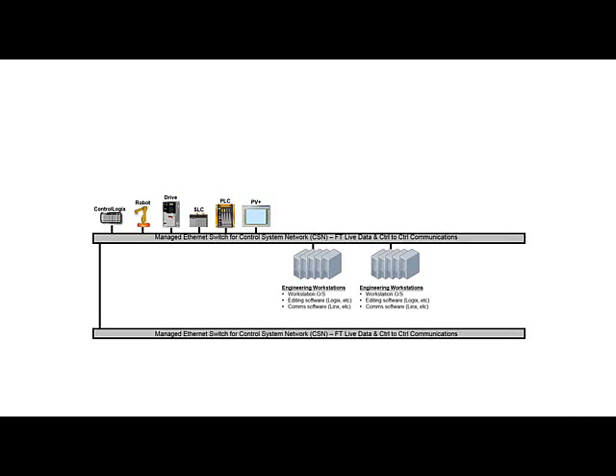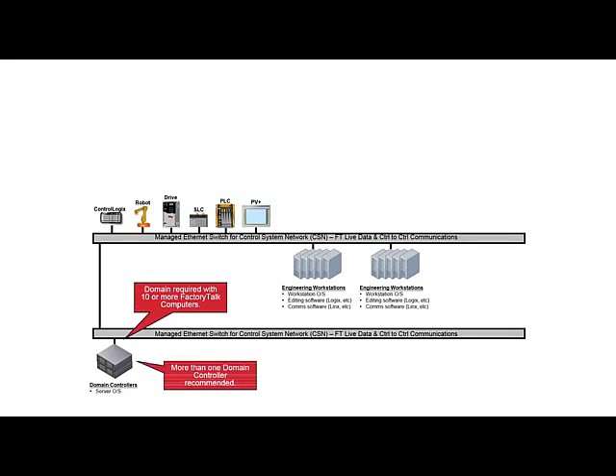Taking the network infrastructure as read, the first thing to consider is the Windows infrastructure. In this example, with 10 engineering workstations already in existence, we know that a domain will be required because FactoryTalk systems require a domain for 10 or more hosts. When implementing a domain, Rockwell commonly recommends at least two domain controllers, allowing for a more highly available domain in the event of a problem on the primary domain controller.